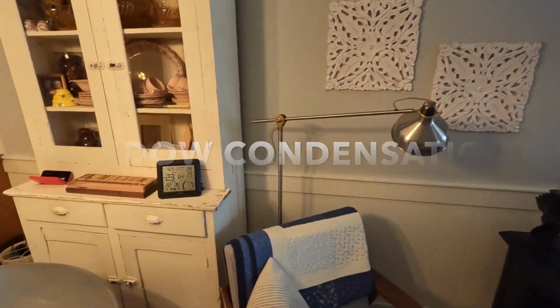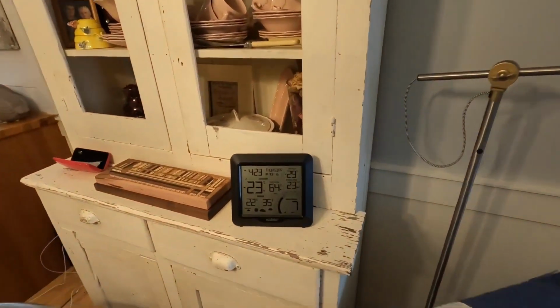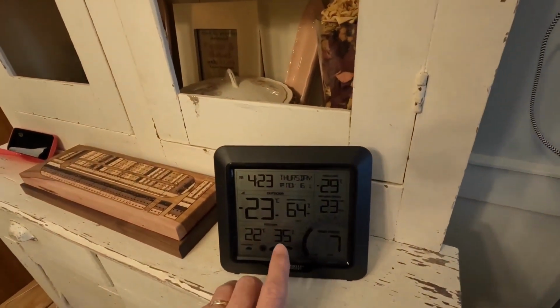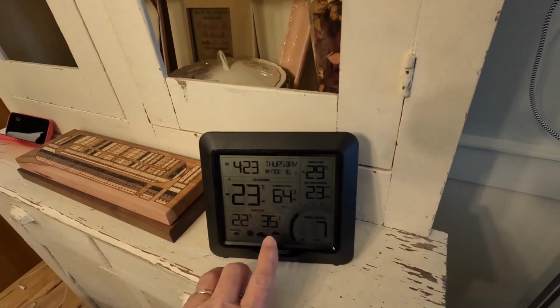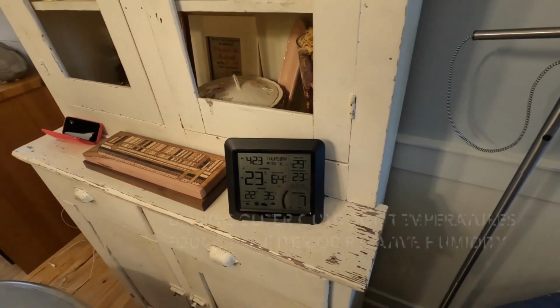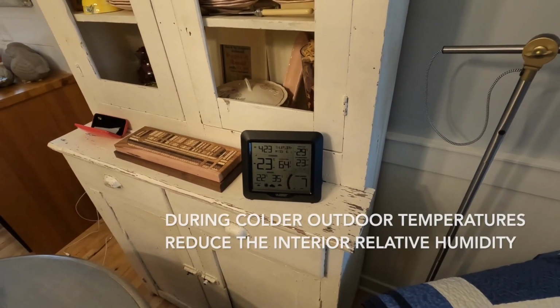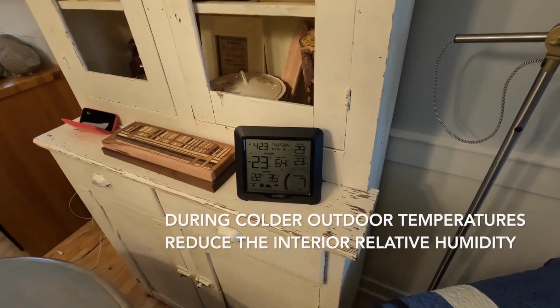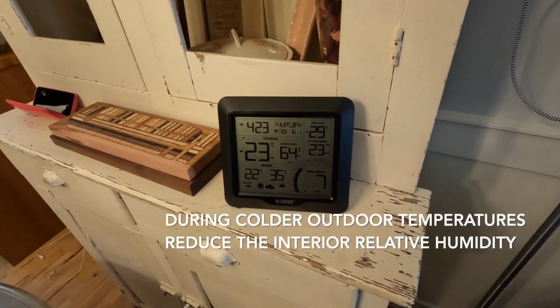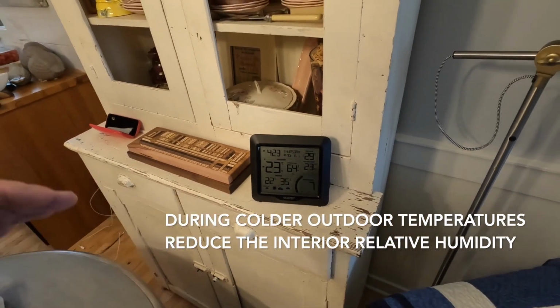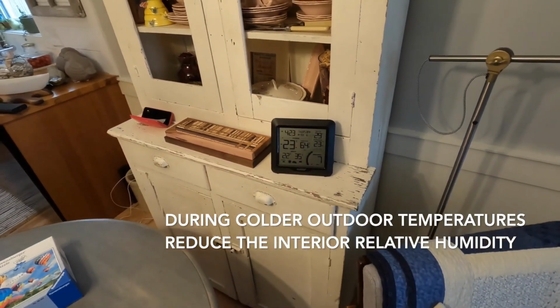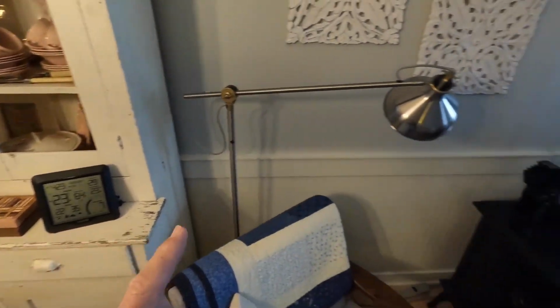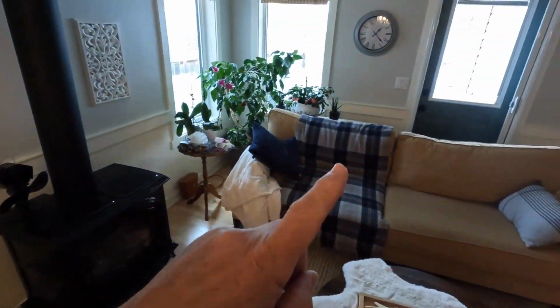Well, one of the causes could be the relative humidity within the building. So down here you can see we're at 35% relative humidity. That's the maximum design humidity for winter under the National Building Code. So the building code says that's the level that we should be able to operate a house without having problems. But that's not the level where we won't have condensation or moisture on the windows.